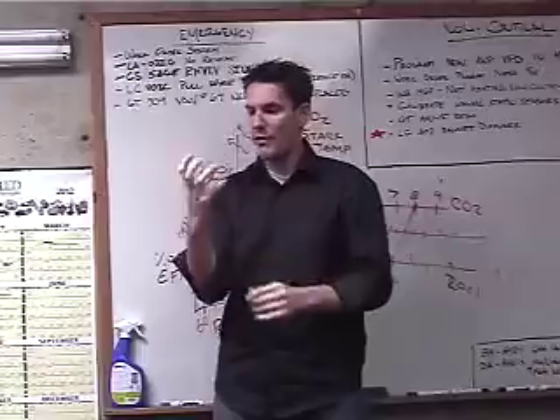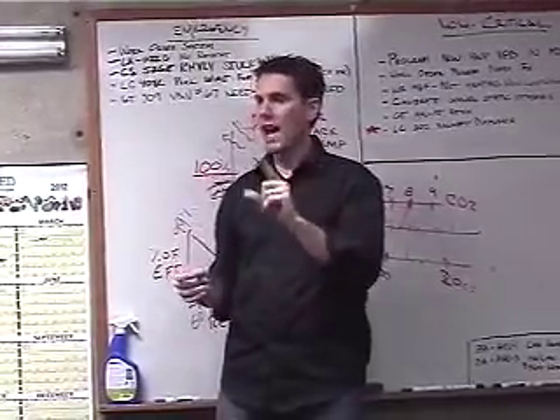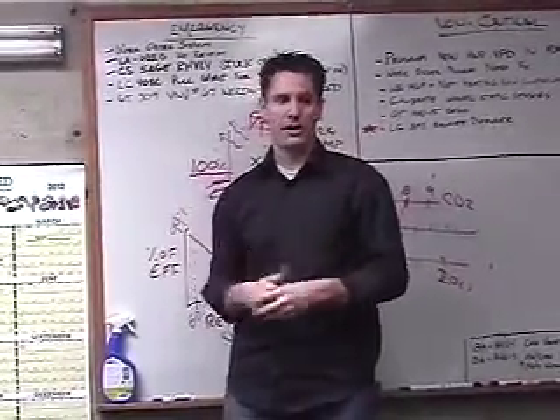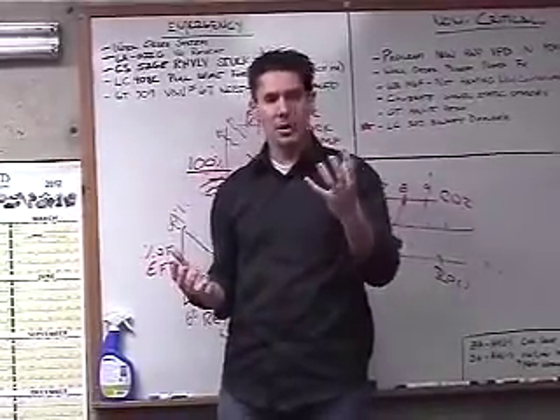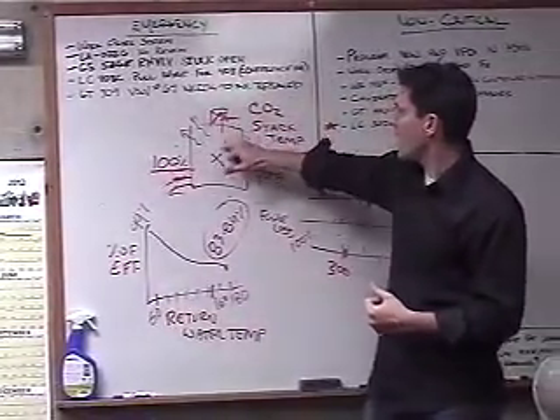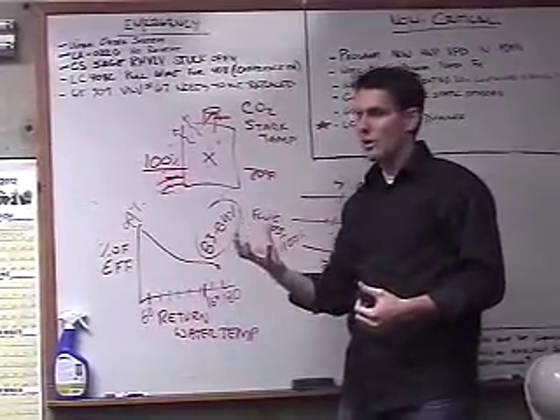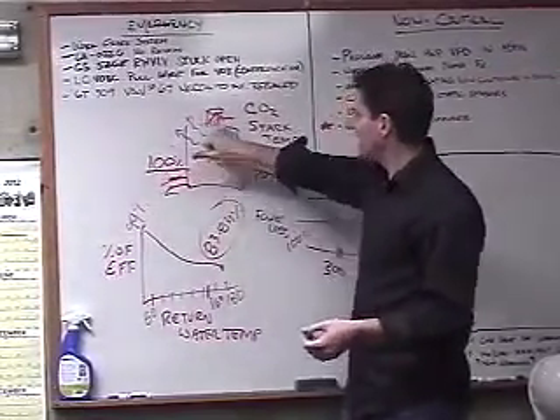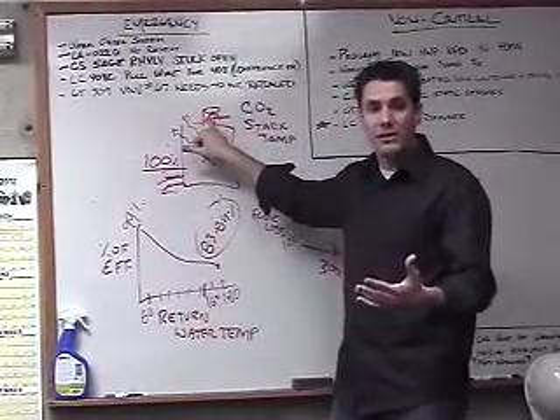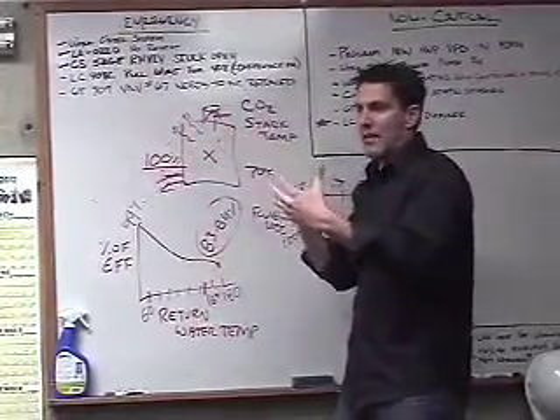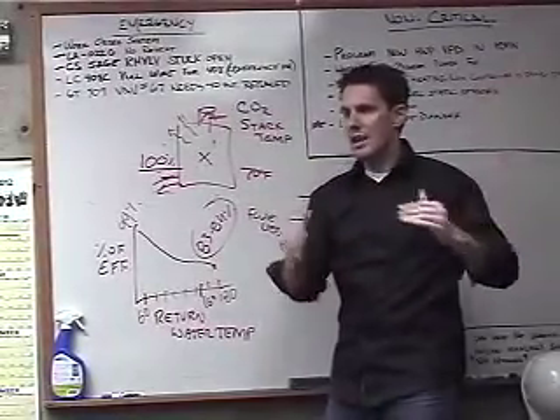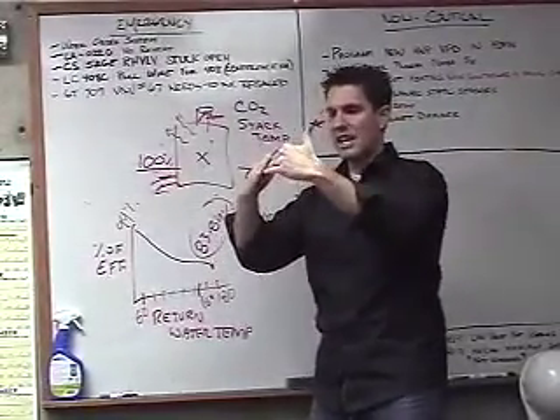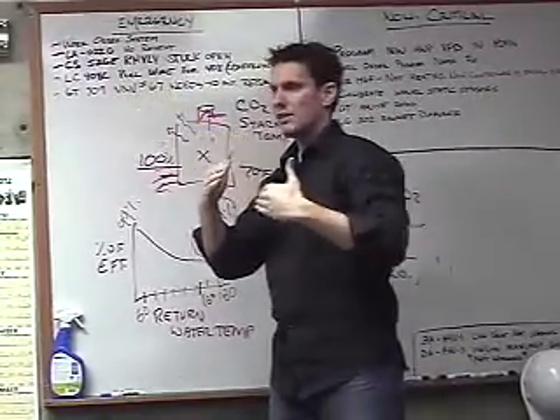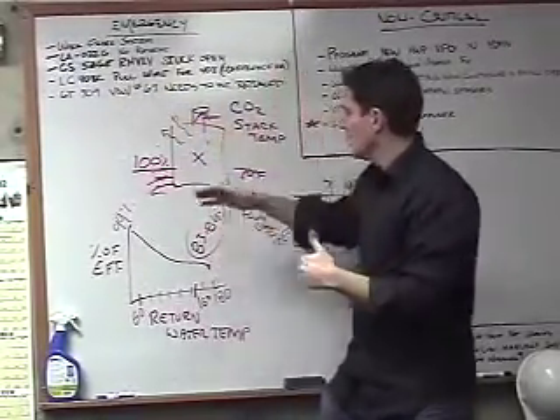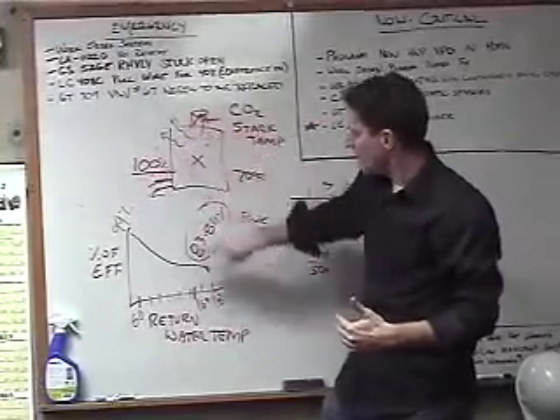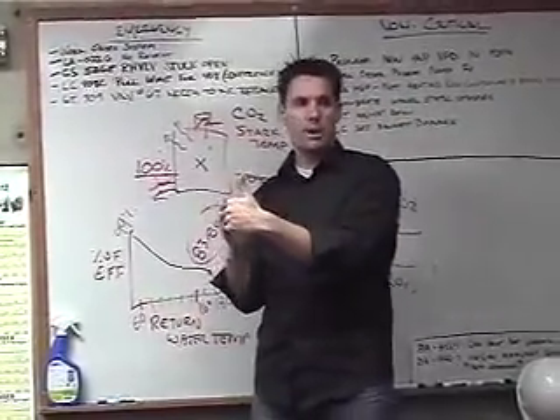It makes sense. So if I have boiling water over here, you will never have a steam boiler that can be greater than 82, 83% efficient. It's impossible. Remember, combustion efficiency, we're measuring how much heat went out my stack. If my water is boiling at 212 degrees, can I send my flue gases out at 105 degrees? I can't pull heat and just stick it anywhere. My water's got to be heated up, and once it's heated up, my flue gas can't continue to cool. That's fundamentally impossible. So the colder I make my water, the more heat I can soak up from my flue gases.